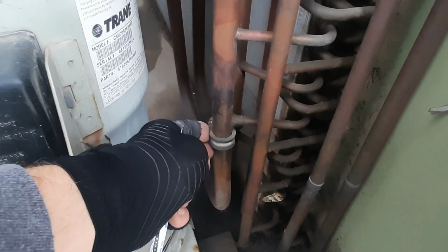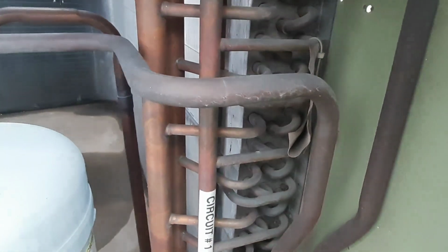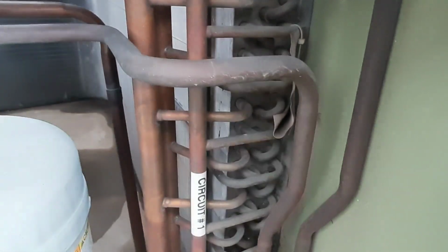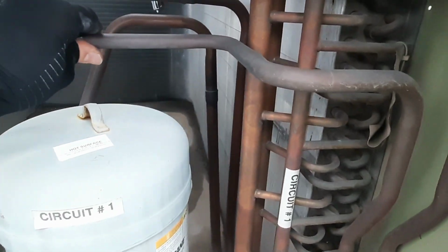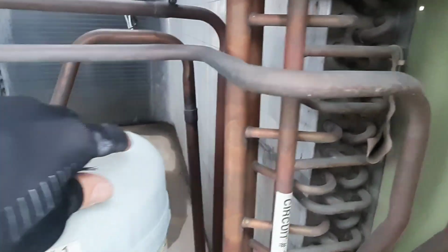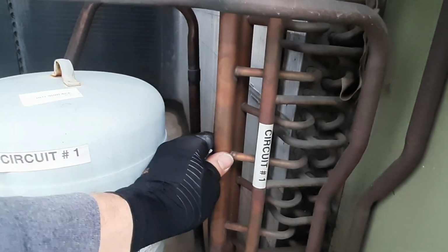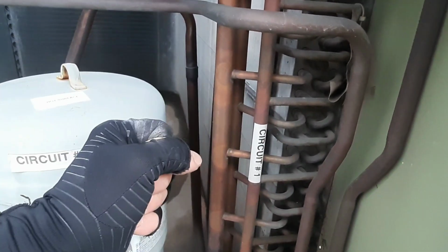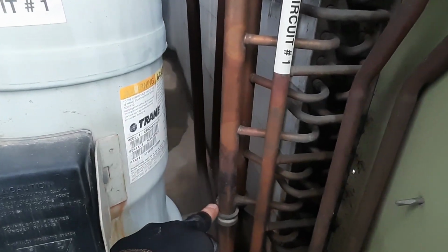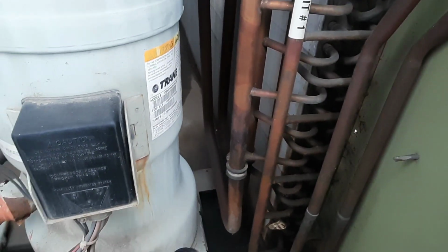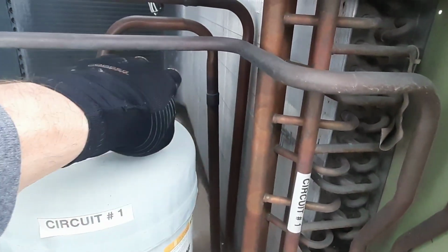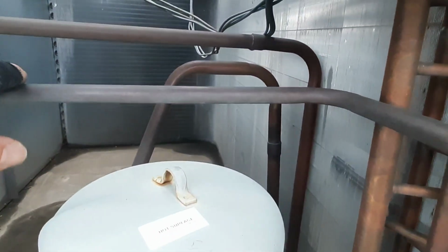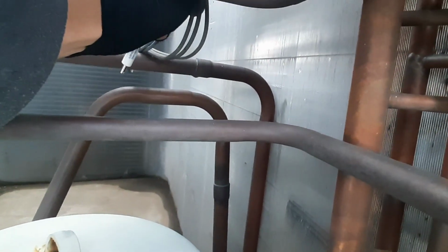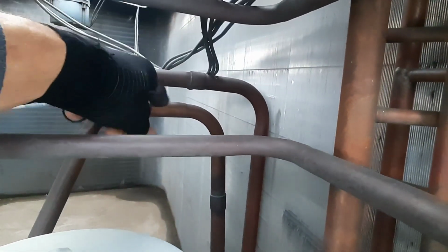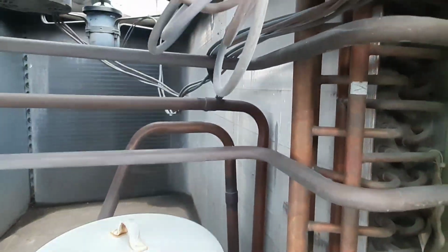So you can see the clamp here. What happens is, you can see that just with the blower running, that discharge line's vibrating a little bit. That's not even a discharge line, that's a liquid line. When these compressors cycle, it jars those discharge lines. So they started clamping them here, and there's a certain weight kit that they put weights on the lines to hold them in place better. Those are rubbing. That's a problem waiting to happen.